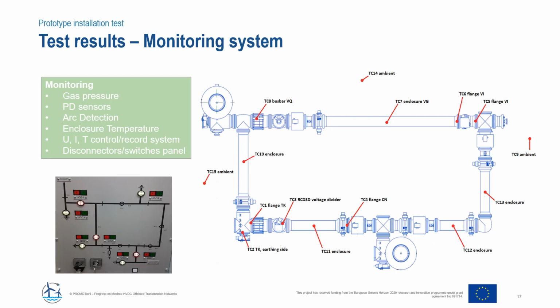And also enclosure temperature has been measured at different locations. Here you see the thermocouples where they are placed, also to compare with the ambient. So there are thermocouples placed in the ambient, in the neighborhood of the GIS, to see the differences between the enclosure temperature and the ambient. There are disconnector and switch panels to show if they are in a closed or open position. Of course, measurements of voltage, current and temperature have been recorded, and this is available, and you will see that in the test results later.